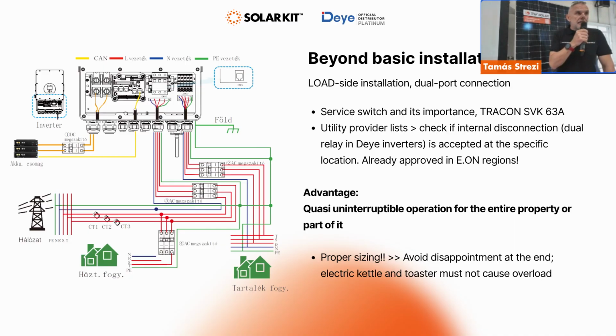In Hungary, it is, with some DNOs. And yeah, we hope it will be allowed in general. So in this operation, they will disconnect from the grid when there is a brownout or blackout or over voltage conditions, which is becoming a more frequent event. What you need to know is that the Deye is always charging the battery even when the grid is down. So that's already a plus.